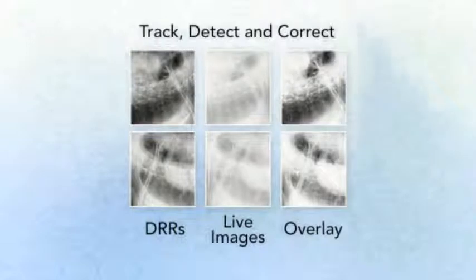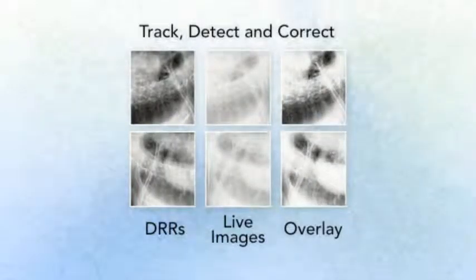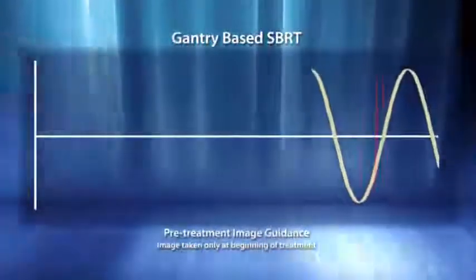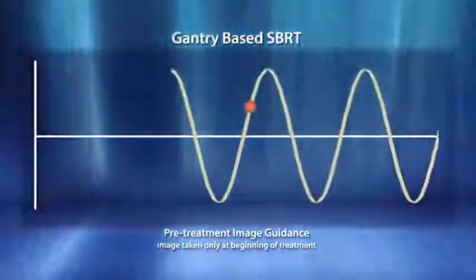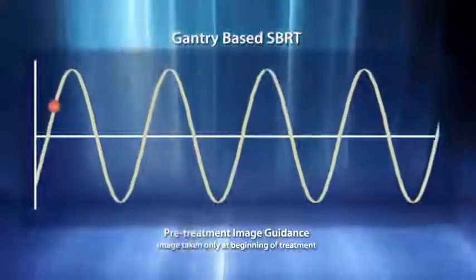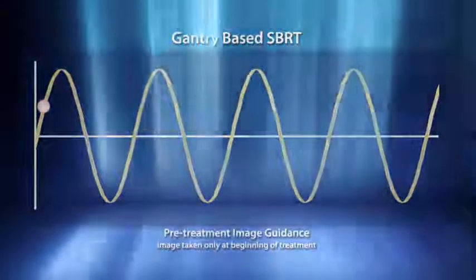With the unique ability to recognize intra-fraction motion, the CyberKnife automatically and seamlessly corrects beam delivery throughout the treatment without requiring clinician intervention, treatment delay, or manually repositioning the patient. Conventional technologies such as IGRT and cone-beam CT only provide image guidance for pre-treatment setup. Therefore, patient and target movements during treatment delivery often remain unrecognized, potentially resulting in increased risk of underdosing the tumor and added toxicity to surrounding sensitive structures.